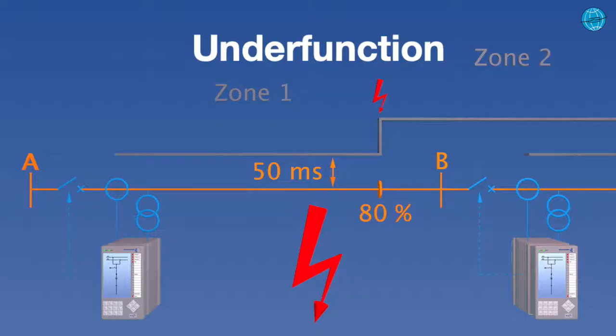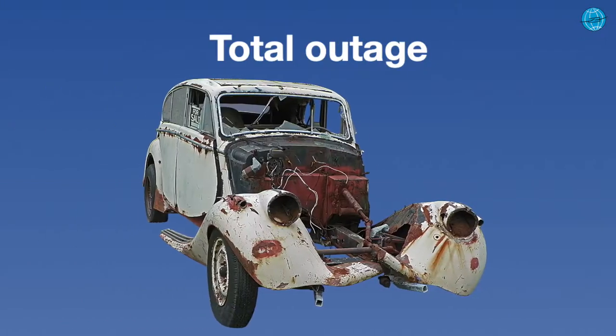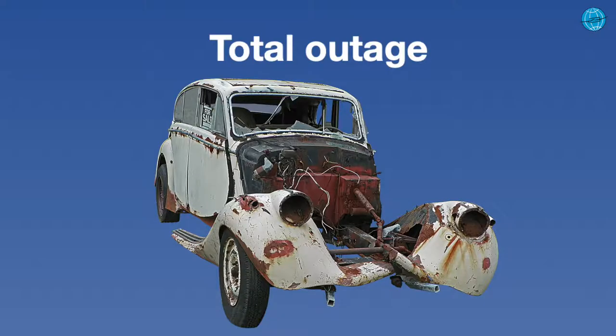Under function would be, for instance, too late distance protection tripping in the wrong zone. Over function are unwanted trips, for instance, a differential protection trip under correct operating conditions or when a transformer is switched on. And finally, total outage is total outage. The protection system kind of hibernates.